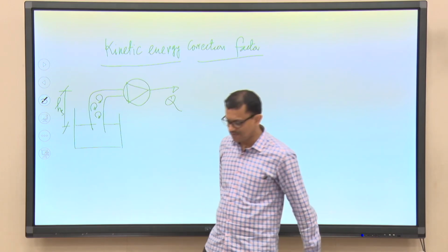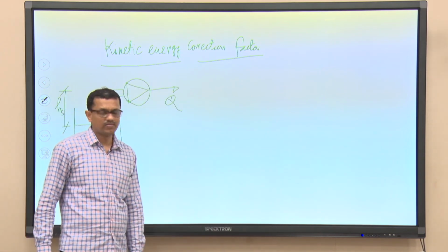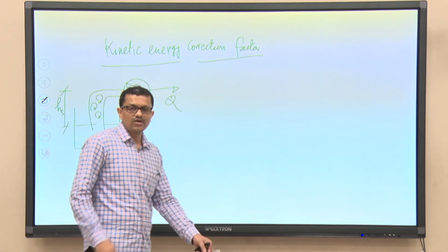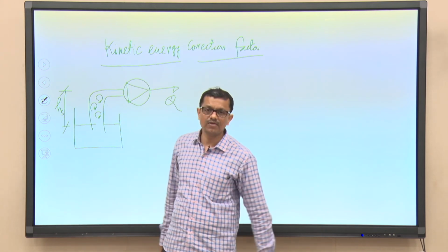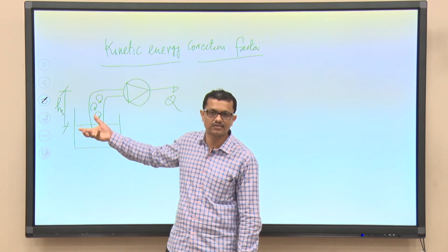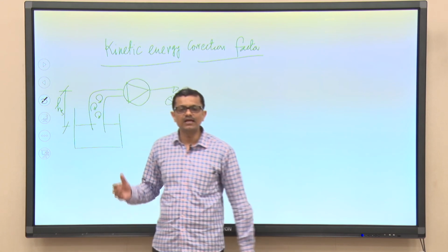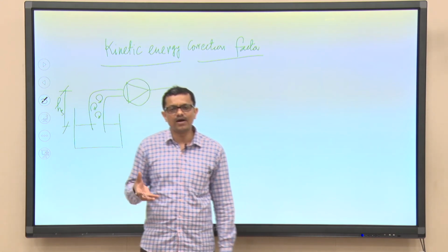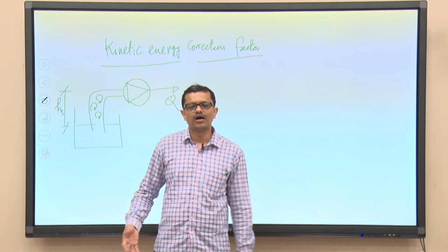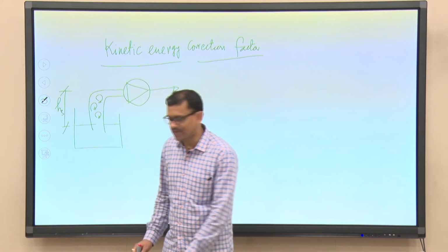The separation losses will be there on account of the non-uniform velocity distribution. So, velocity distribution is not uniform. If we calculate everything considering that velocity is uniform, then the loss of energy due to the formation of eddies and their sustenance will not be accounted for, and probably we will design the pump, but when the pump is placed in a pumping station, we will encounter different problems for its smooth operation.